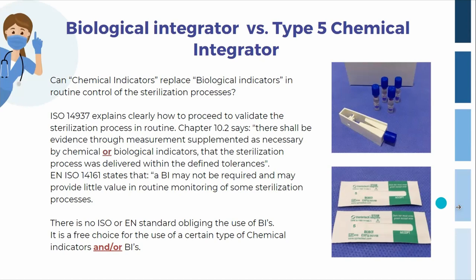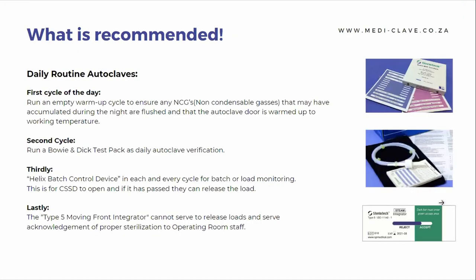So what is recommended? We recommend your first cycle of the day to be a warm-up cycle, or if you don't have a warm-up cycle on your autoclave, just run an empty cycle for any non-condensable gases that may have accumulated during the night, or even if your autoclave is switched off at night, just to warm up the door as well as the rest of the autoclave. Your second cycle will be to run your Bowie-Dick test pack as a daily autoclave verification.